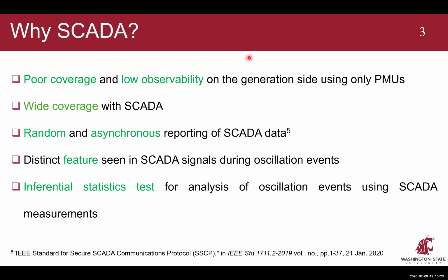We have typically thousands or tens of thousands of SCADA measurements compared to hundreds of PMU measurements. And so that's the main motivation. But then again, the advantage of PMU, we know, is synchronized sampling and also high speed, typically either 30 hertz or 60 hertz in this country. Even 120 hertz is now being discussed. So it seems appropriate for analyzing oscillations using PMUs. On the other hand, SCADA scan rate is typically much slower. It may be as slow as once in 10 seconds. Some of them have fast SCADA systems, maybe once in half a second, but still, these are significantly slower compared to PMU reporting rate.